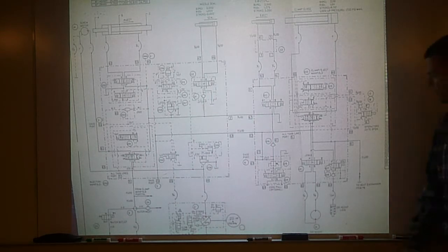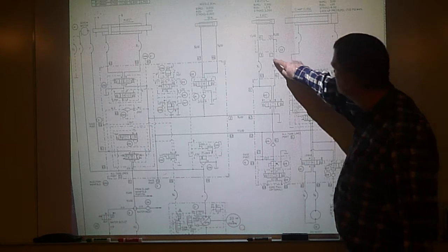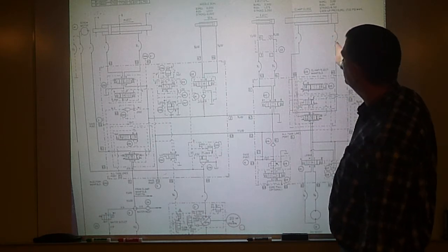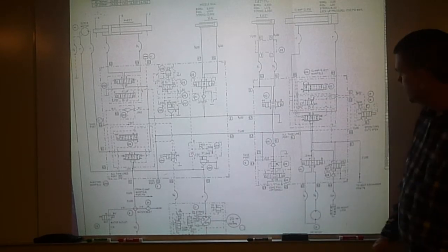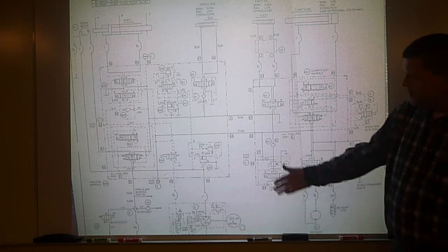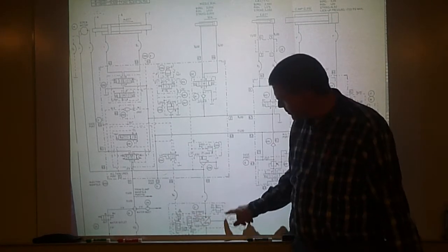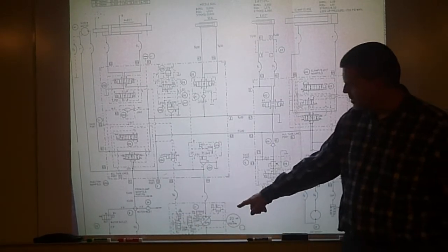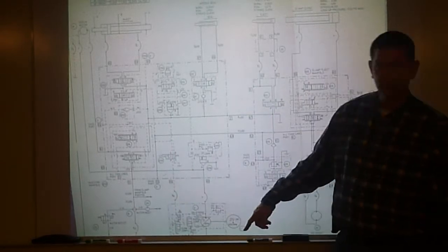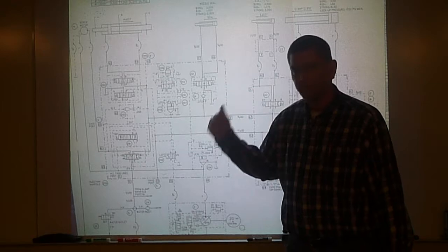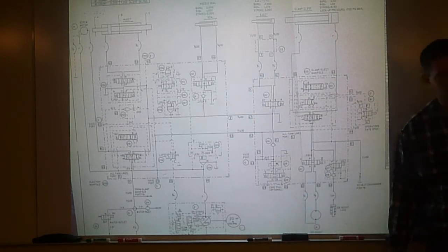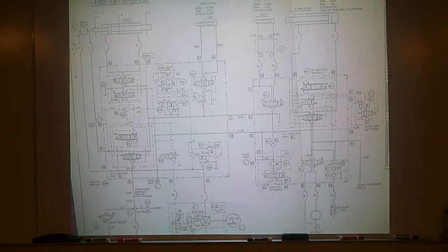Something else we talked about very briefly in the class. Every one of these little loops here, or half loops, they're all over the place in this drawing. Those are hoses. We always connect pumps by hoses. That isolates this whole thing. It represents an assembly. The pump assembly is isolated from the rest of the system. We do that because we don't want to put the vibration through all the steel lines that typically feed all your devices. So, understand that.